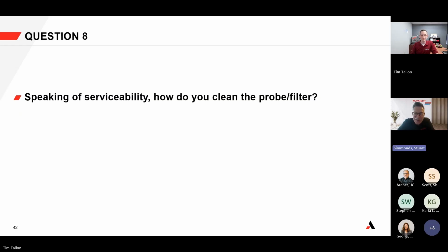We in analyzers know it's always a fatal mistake for analyzer manufacturers or sellers like us to overstate things, to say there's no maintenance, you'll never touch it. It's always a dangerous thing to say. I think it's better to say most process analyzers have some amount of service requirement, depending on the application, depending on where they go, and many other factors. So it's better to hit it head on, and in combustion control, serviceability is a big deal. It's how do we keep these things up and running? They're often in critical service, sometimes even in control mode, so how do we keep them running as best we can and predict that as we go along? I guess that's the big question here.